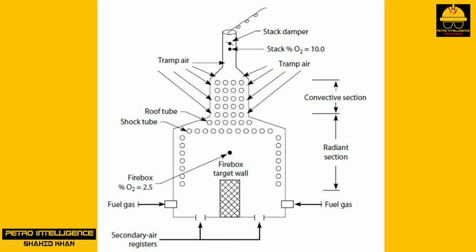If we intend to install an oxygen analyzer, the analyzer should be monitoring oxygen in the firebox itself. Lone oxygen analyzers monitoring oxygen in the convective section are misleading as a result of the tramp air and are a positive hazard to safe operation.